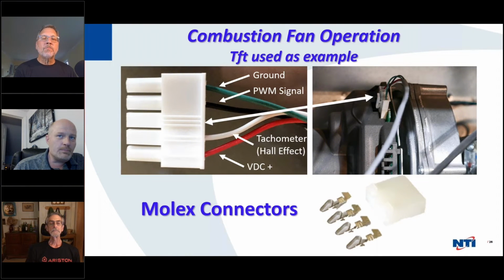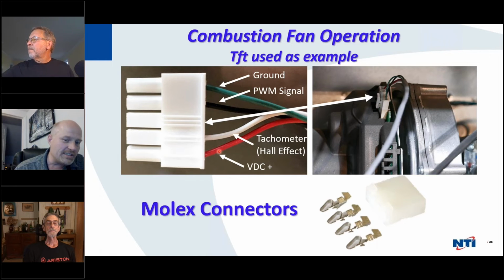When we measure it in the field, we measure it like a DC voltage on our voltmeters. Technically speaking, it's a PWM signal, which is pulse width modulation. And we won't get into that today, but basically pulse width modulation is you're turning on and off a voltage signal very, very fast, in this case around 20 or 30,000 times per second. And what our voltmeters end up seeing is they average the voltage. So if the power's on 50% of the time and it's going from 30 to 0, 20,000 times a second, your voltmeter is going to average that out for you, and it's going to show you 15 volts as an example. So what we get you to measure in the field, we'll get you to go between black and red. You measure the difference between these with your voltmeter set to DC volts.